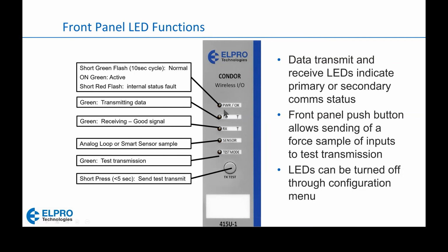Obviously, we have our power and OK LED, and it just flashes once every 10 seconds in normal operation. Then we have our TX and RX LEDs, and they flicker whenever sending or receiving. The RX LED is dual color—it flashes green when we have a strong signal, red when we're receiving a weak signal. And this one turns on whenever we're taking a sample from a 4-20 milliamp or an SDI input.